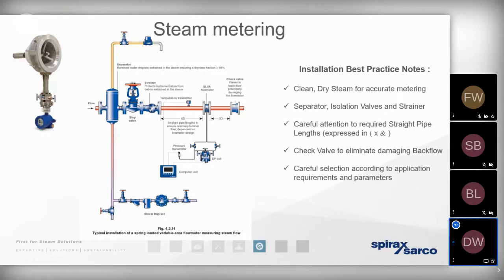So we want to remove the moisture and the debris, the particulate, so it doesn't create erosion problems. We want to vent the air away. We want to remove the condensate. We want to have a correct run of pipework upstream and downstream to maintain linear flow. We want to install a check valve so that we don't have a massive condensate being pulled back across the steam meter if we get fluctuating pressures on the steam side.